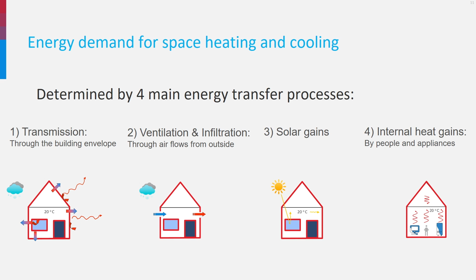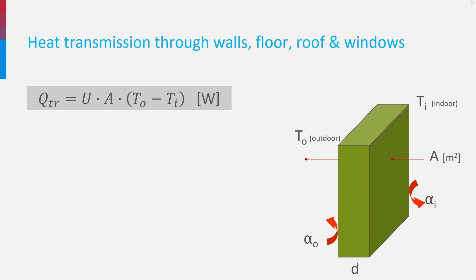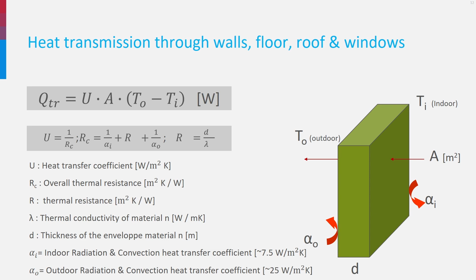Now that you have learned how to make an energy balance, let's look at how to calculate the different parts of the balance. Let's start with the heat transmission through the envelope. You see on the picture right a wall, but it would be exactly the same for a floor, roof or a window. The heat transferred by transmission is calculated as a function of the temperature difference between outdoor and indoor, the surface area A of the wall and the heat transfer coefficient U, which is the inverse of the heat resistance R. The heat resistance of the material itself depends on its thickness and its thermal conductivity.